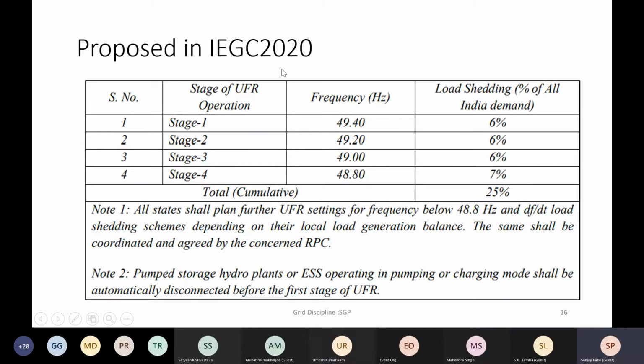The Grid Code 2020 gives recommendations for load shedding schemes starting from 49.4. So you can see that from 49.5 your narrow band of operation starts, and just below that at 49.4, in steps of 6% of all India demand, the load has to be shed as the frequency goes down from 49.5 to 49.4, 49.2, 49, and then 48.8. And this is the quantum of load shedding. So almost 25% of the load can be shed with this under frequency load shedding scheme. That is what is proposed.